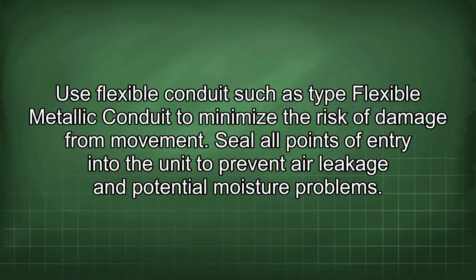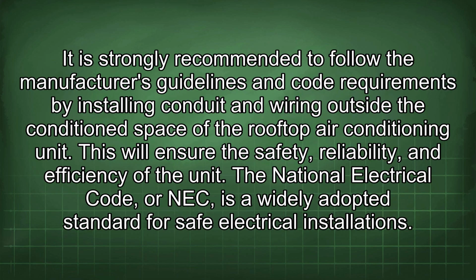Use flexible conduit, such as type Flexible Metallic Conduit, to minimize the risk of damage from movement. Seal all points of entry into the unit to prevent air leakage and potential moisture problems. It is strongly recommended to follow the manufacturer's guidelines and code requirements by installing conduit and wiring outside the conditioned space of the rooftop air conditioning unit. This will ensure the safety, reliability, and efficiency of the unit.